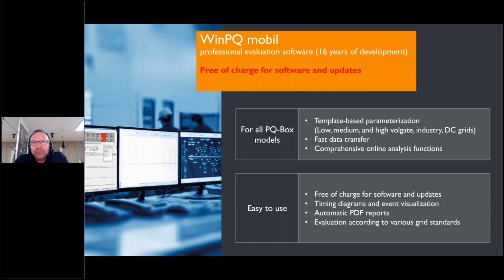With big, powerful software, we have been working on our WinPQ mobile software for more than 16 years. The high-end software delivers a lot of automatic reports, nice graphic views, and helps you analyze what you are interested in within big data. Our analyzers always measure a lot of data. If you press the start button of a PQ-Box 150, for example, we measure more than 3,000 different parameters, and you do not want to analyze them all after your measurement. So you need professional software that tells you what is interesting in all this data.